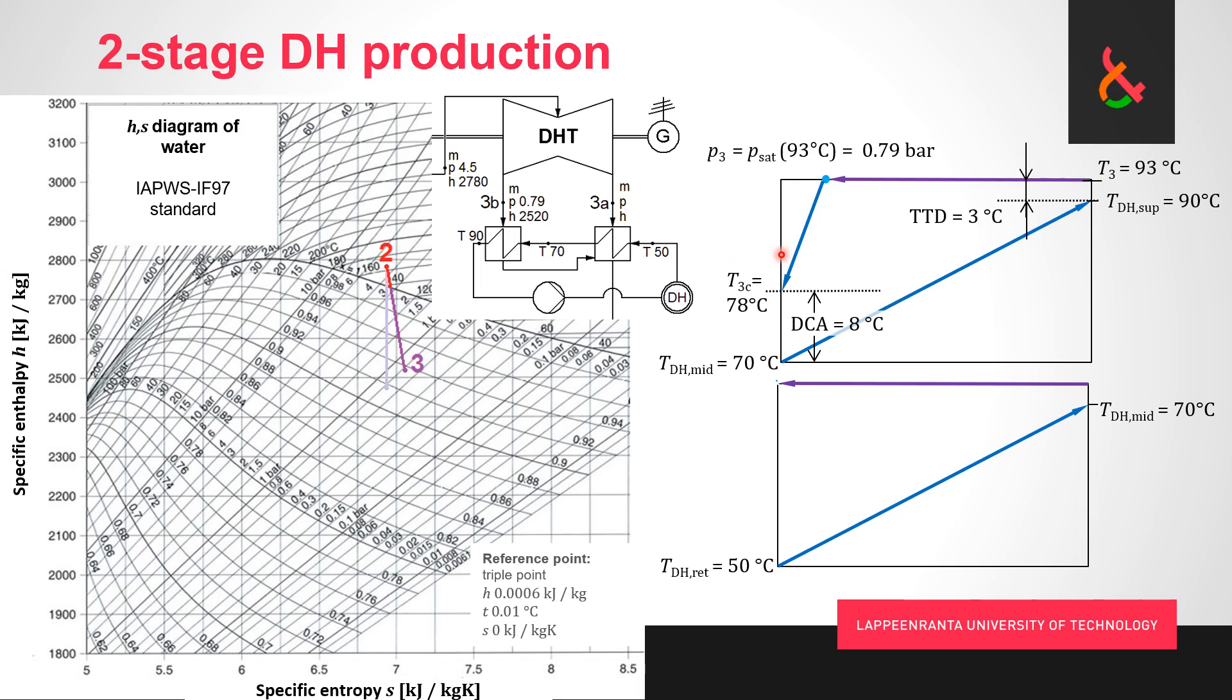The other reason is purely practical and mechanical. If we don't subcool here, when this condensate is sent to the shell side of the lower pressure condenser, some of the saturated condensate liquid would flash into steam, and that is a pretty violent phenomenon. We can handle it with an impingement plate, but we don't want to make our life more difficult than it has to be and don't want to consume and destroy that impingement plate. Better also from that perspective to subcool it. This way there's going to be some flashing but a whole lot less.